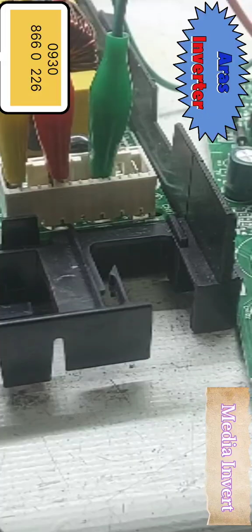The internal PCB you are inspecting is the most probable culprit, specifically the section responsible for driving the outdoor fan motor. Error code P4: failure to start outdoor fan motor. This is the primary and likely root cause.